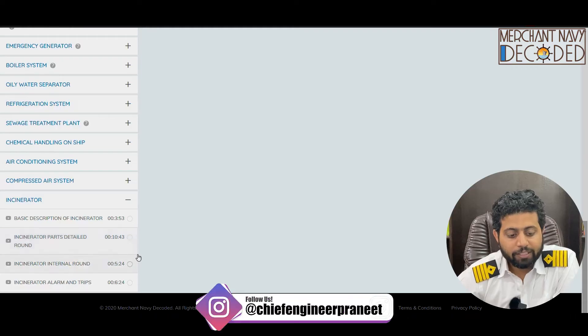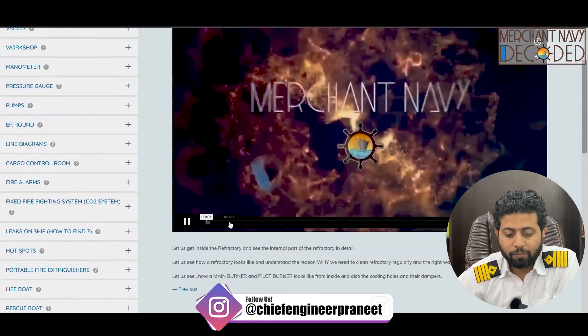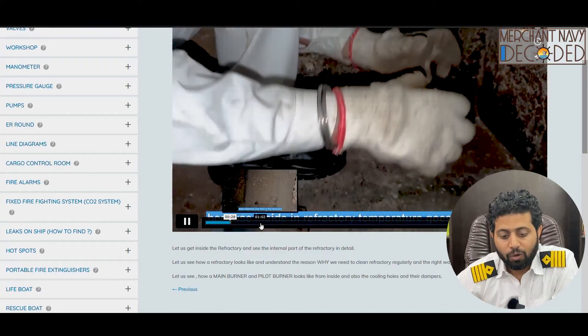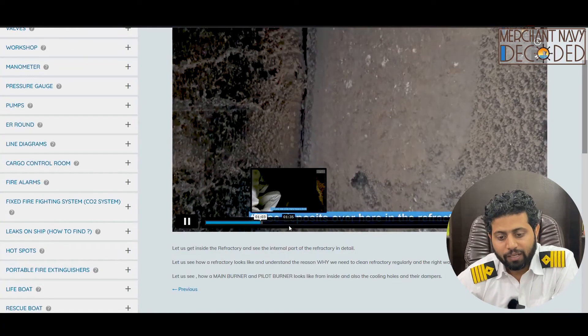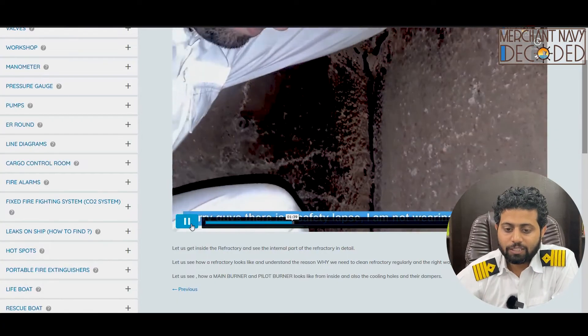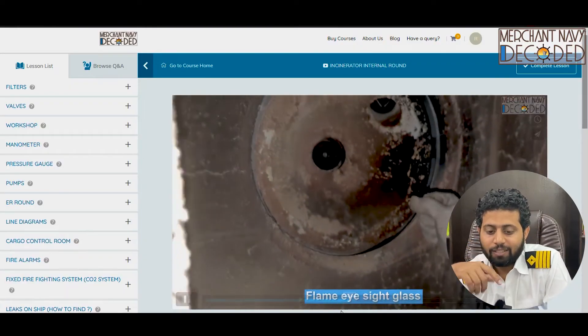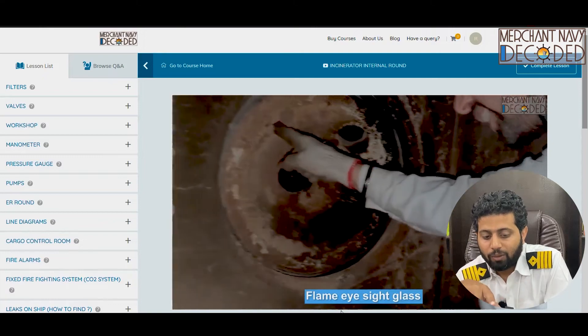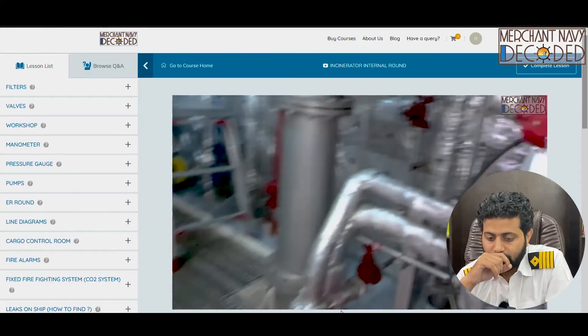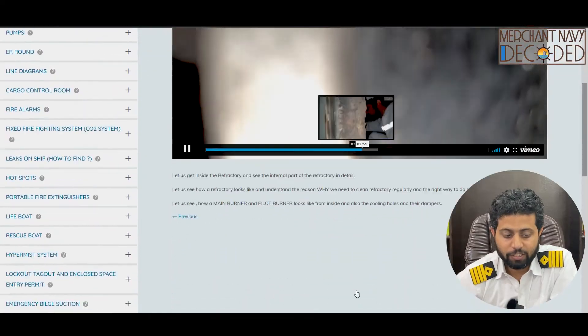Next is the incinerator internal round. In this video I go inside the incinerator to show how it looks from inside, how we take care of the refractory, what we need to do with it, how to clean the refractory, and how the main burner and pilot burner look from inside. I am inside the refractory showing the flame eye, the main burner, the pilot burner from inside, all safety precautions, and the sight glass from where we observe whether the incinerator is firing or not.